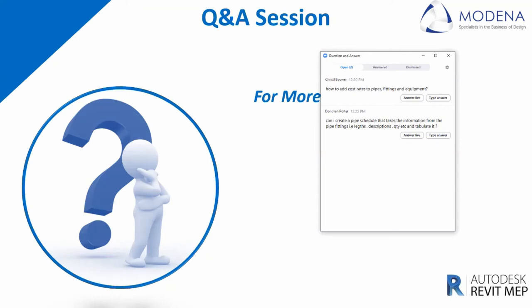We've got another question from Christelle: how do you add cost rates to pipes, fittings, and equipment? Equipment is actually the easiest element to add costings for — in your edit type box you'll find a costing parameter and you add the value to the equipment or fixture itself. However, when it comes to fittings and pipes, you'll have to add that within the schedule under what we call a calculated parameter. You create a parameter with a formula-based element — for example, cost for pipe — where you write the length divided by one metre for a per-metre cost. The reason we divide by 1000 is because Revit constantly reads in millimetres. So by dividing by that one-metre mark, we get a value which we can bind to a cost. In my formulas, it was length divided by 1000 multiplied by the price, giving a basic cost for the piping.